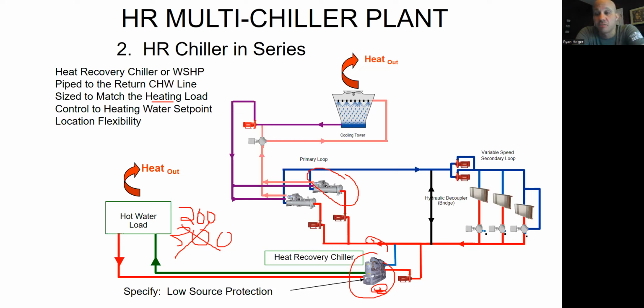Or it could be the opposite. Let's say you need 300 tons of heating and 250 of cooling, right? You could just not buy a cooling tower, put all the heat into the hot water loop, and then you'd need a boiler to give me another 50 tons of heating.